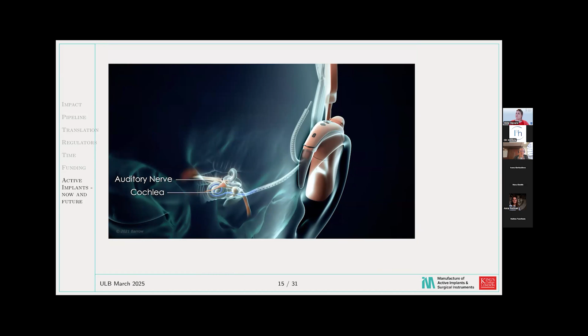But there is also an implanted part underneath the skin and slightly embedded into the skull. They dig a very small cavity to place the implant, and then the electrode array is inserted into the cochlea. I'm going to zoom in onto that area. This is where there's a very small window into the cochlea, and the surgeons, with extreme precision, have to push the electrode array, which has to be made solid enough, resistant enough to go through the window, but flexible enough to curve into the cochlea, becoming thinner and thinner in its design so that it can reach at least 2 to 2.5 turns into the cochlea.